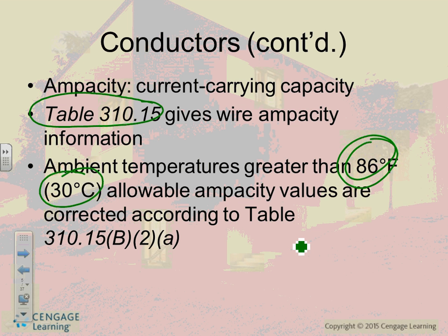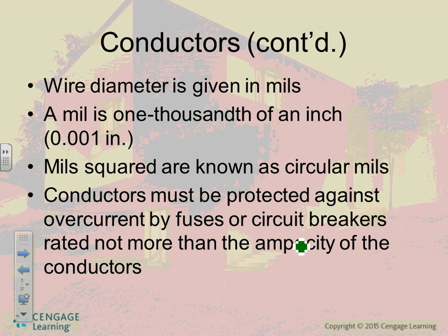The table for derating, guys, is this one. We'll be looking at it in a second. We looked at it last time. If you remember, we were looking at the temperature and wire diameter. What's a mil? After the conductors, we take from number 40 all the way to number 1, and then they go 1/0, and then 2/0, 3/0, and 4/0.